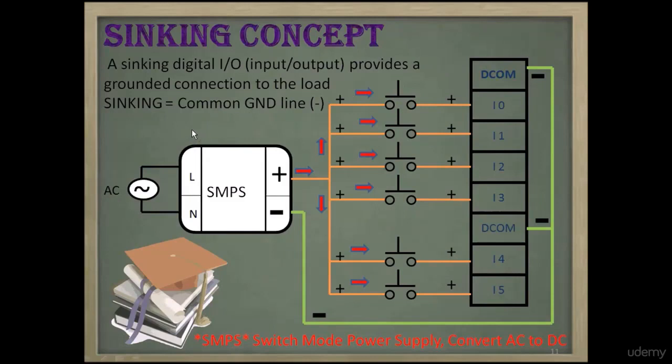Therefore, start at the PLC input terminal and follow through the input sensing circuit, exiting at the common terminal. Connect the supply to the common terminal, adding a switch between the supply and the input so that the circuit is completed and current flows in the circuit when the switch is closed. The arrowheads represent the direction of current flow in the diagram.